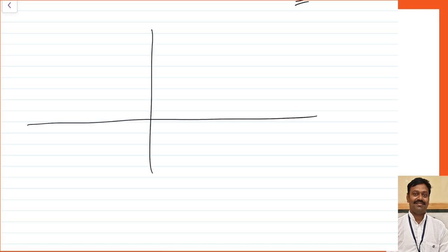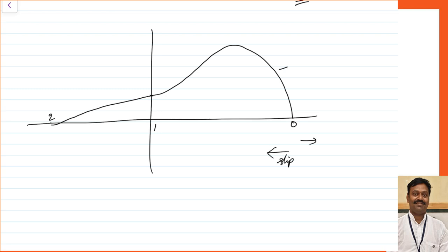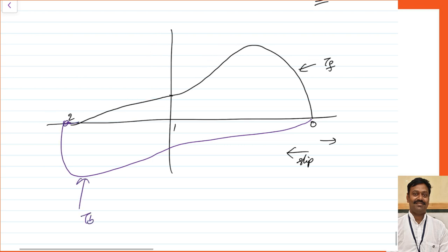There is another way to analyze this using the induction motor torque-slip curve. We have the torque versus slip curve for the forward rotating field. If extended, it goes from slip = 0 to slip = 1 and slip = 2. Similarly, for the backward rotating field rotating in the opposite direction, the torque curve is a mirror image — starting from slip = 2 going backwards. At the standstill condition (slip = 1 for forward), the forward torque equals the backward torque, so net torque equals zero. The forward torque equals the reverse torque at standstill.